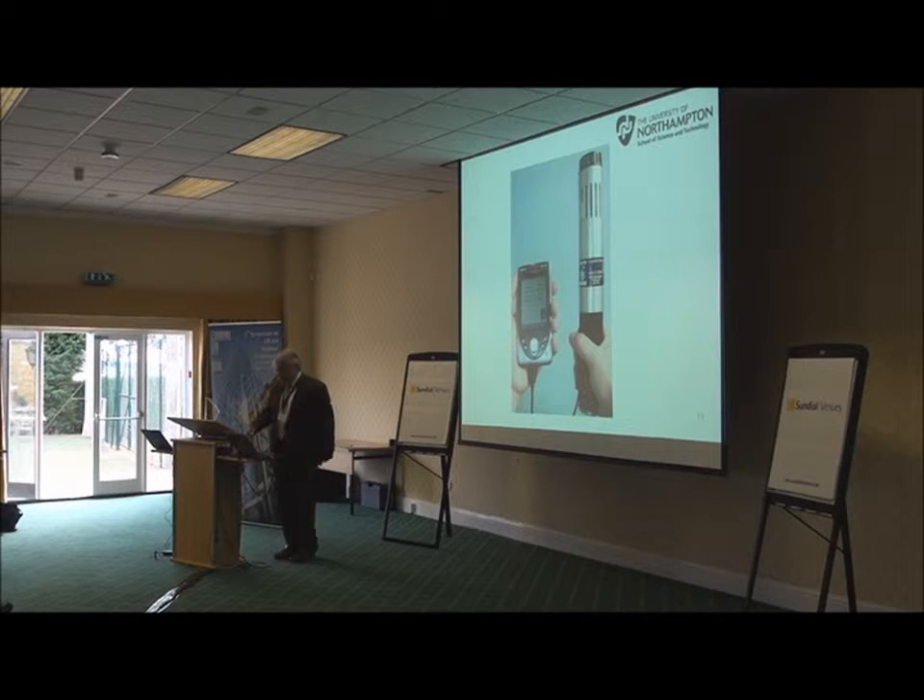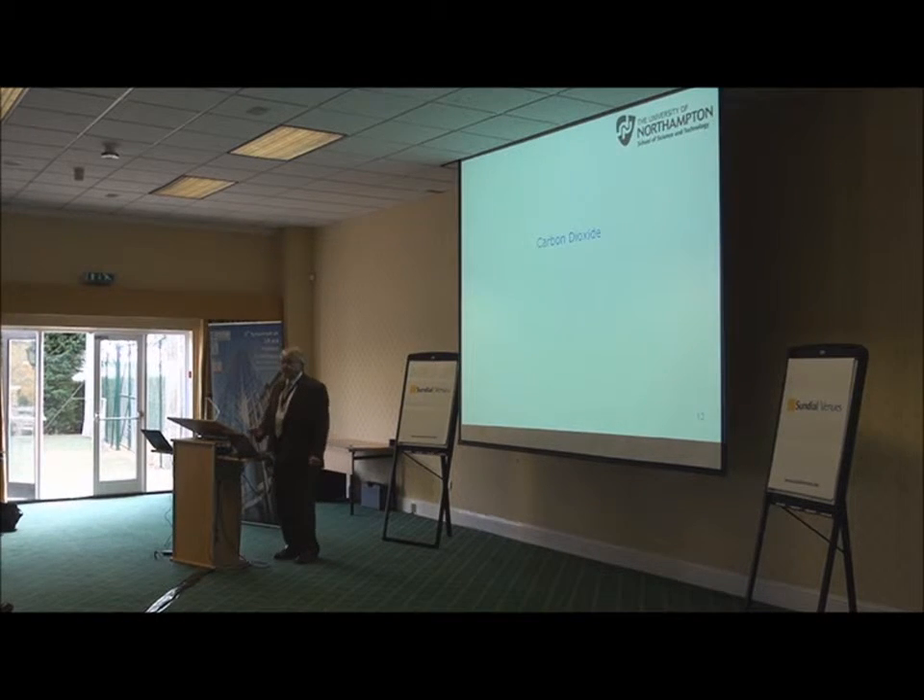We used a device that measures air quality made by a company called Gray Wolf from Connecticut in the United States. It measures carbon dioxide, carbon monoxide, and total volatile organic compounds (TVOCs). TVOCs are a big thing in building air quality, generally relating to volatile compounds from flooring, ceiling, and walls. In this case, what TVOCs represented was human effluent — an elegant word for body odor. It's not toxic, but it's offensive.